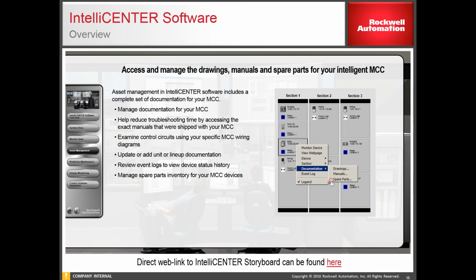And then again, in terms of the documentation, all the documentation associated with all the devices that are in your MCC is going to be a part of this software package. So all the wiring schematics, all the manuals. So if you've got E300s, if you've got drives, if you've got soft starts, all the documentation is going to be a part of this package. So you don't have to go looking for information. It's right at your fingertips within the software package. Right, so you click on the device, you go to the documentation, and then you pull up whether it's drawings or manuals or spare parts. All that information resides right in the software. Okay?